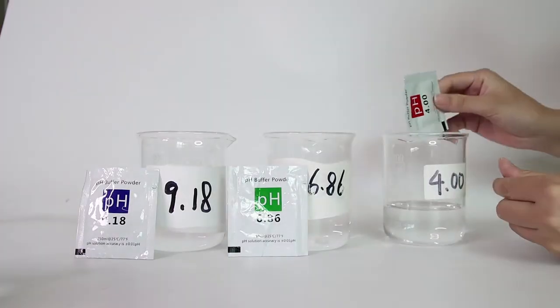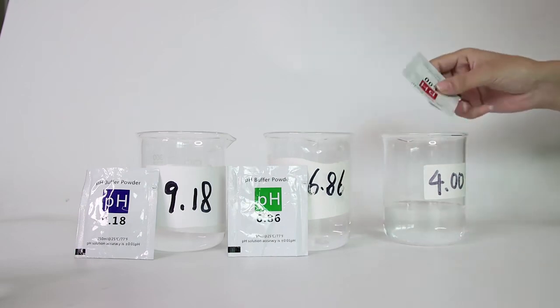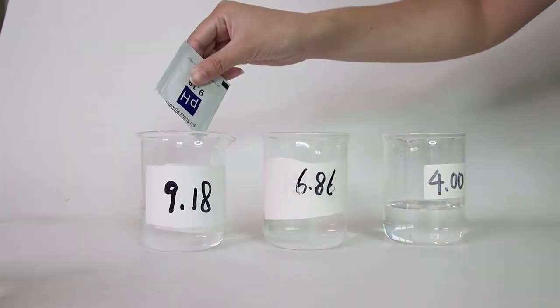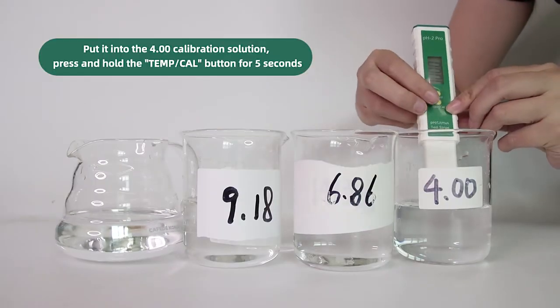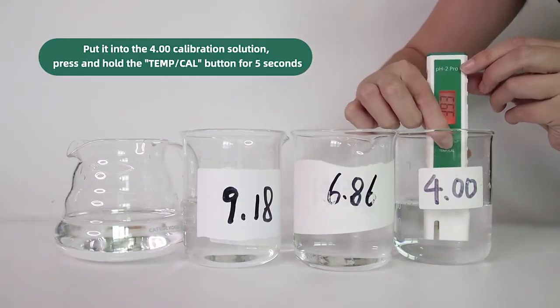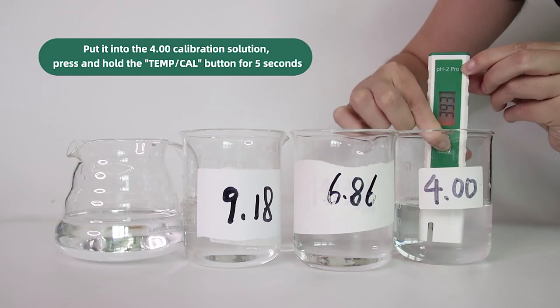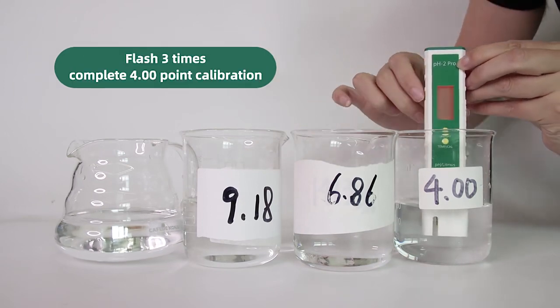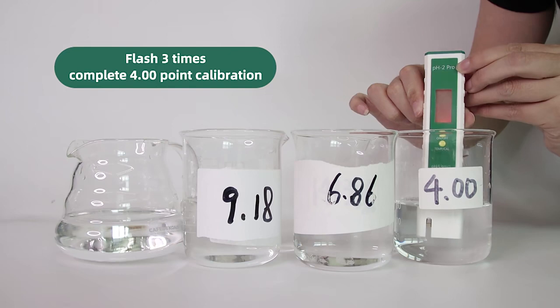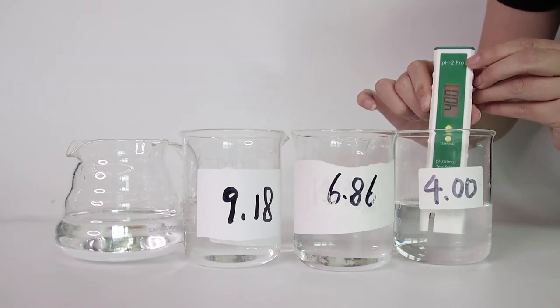Calibration demo. Pour the 4.00, 6.86, 9.18 powder into the container and gently stir. Put it into the 4.00 calibration solution. Press and hold the temp Cal button for 5 seconds.